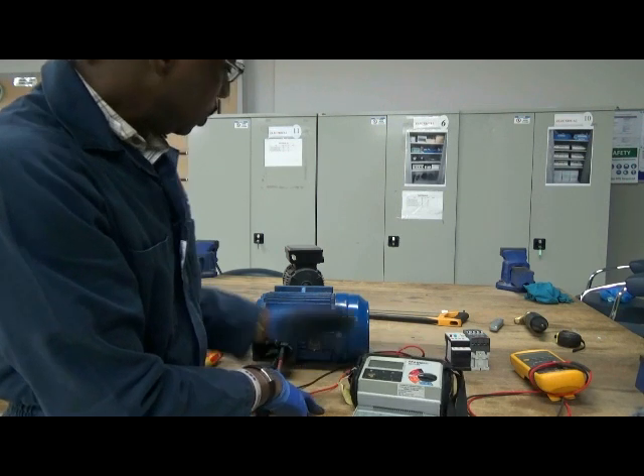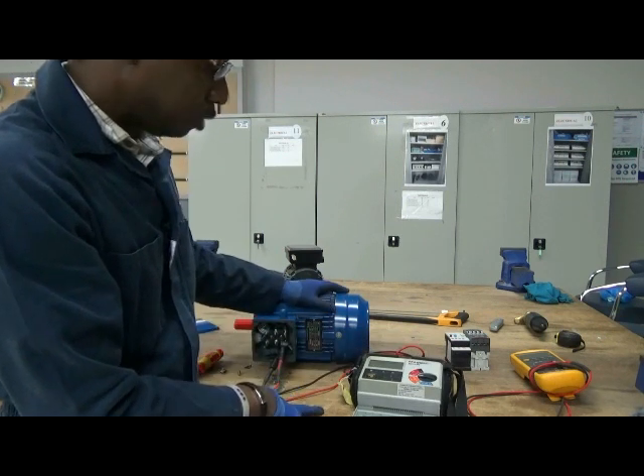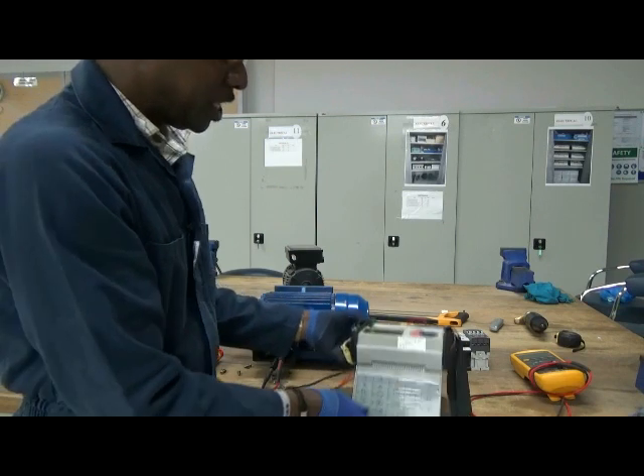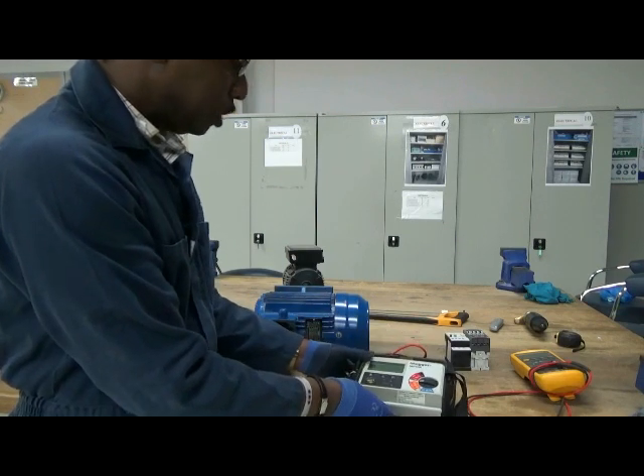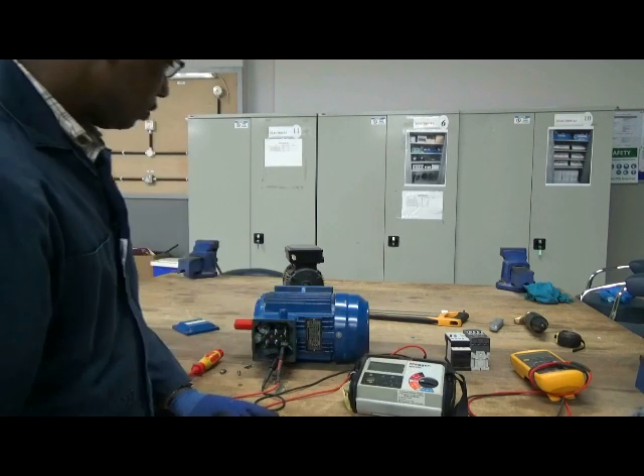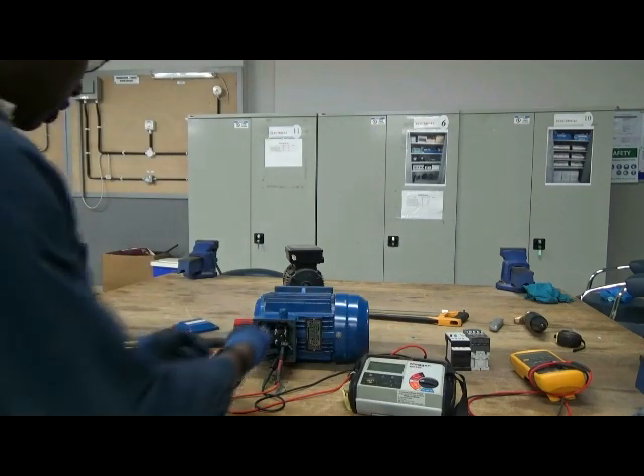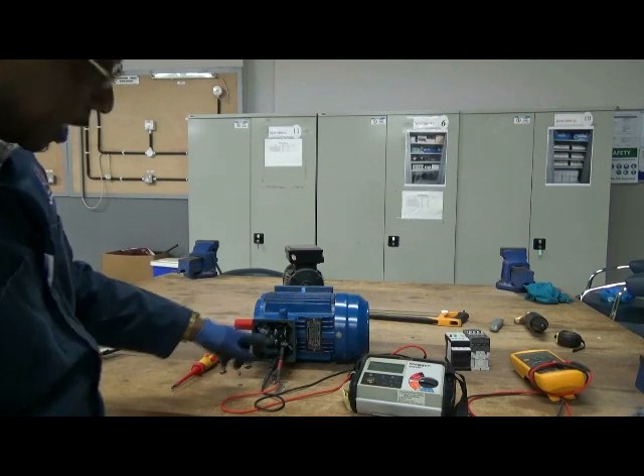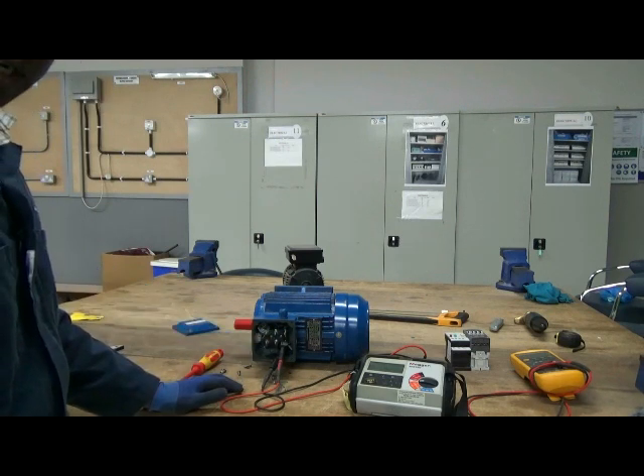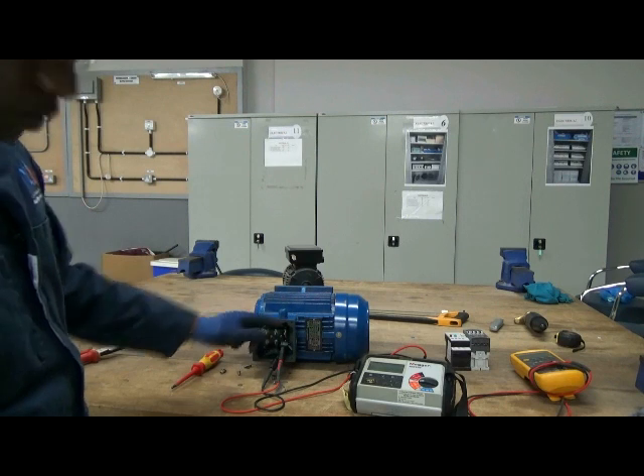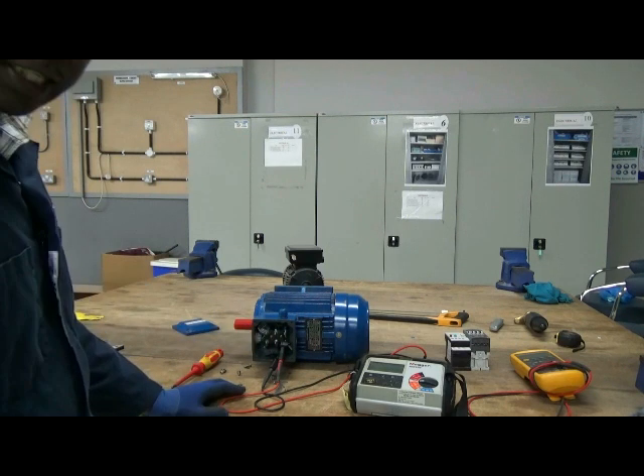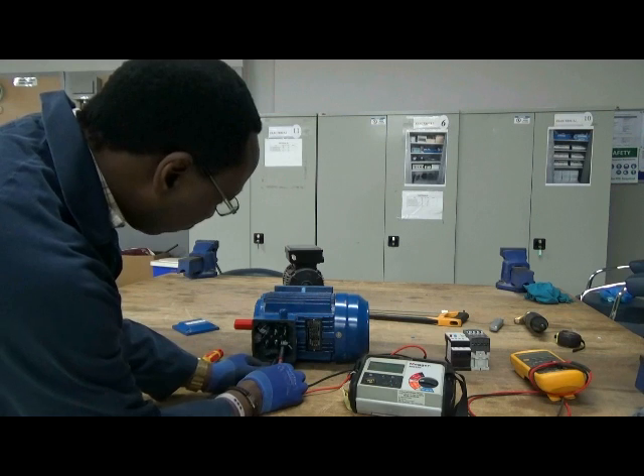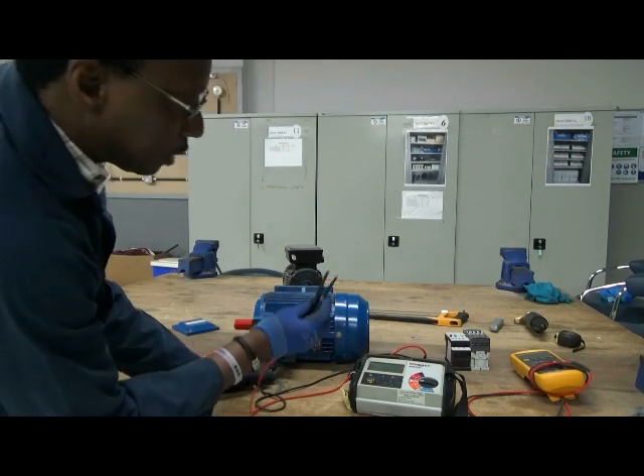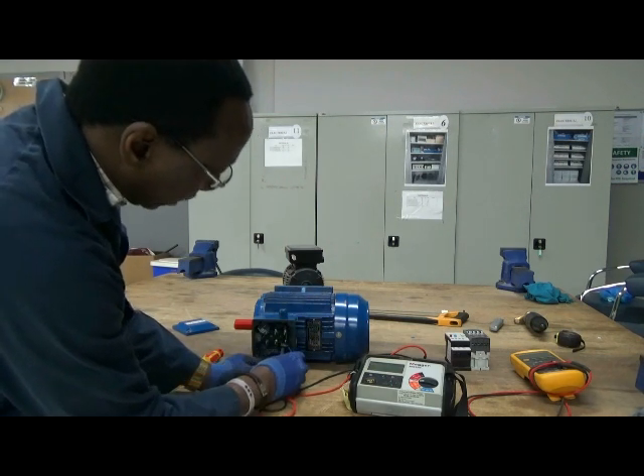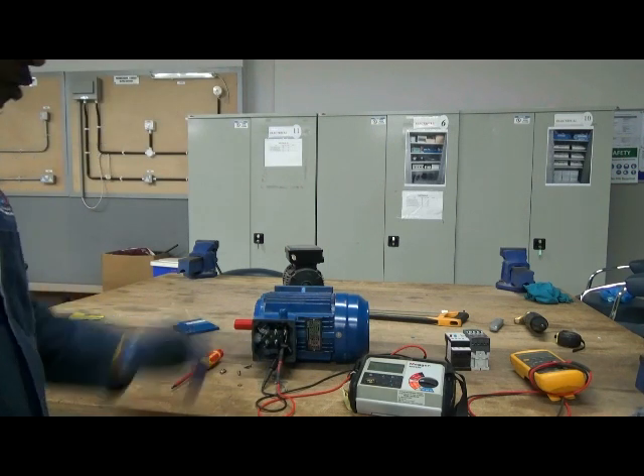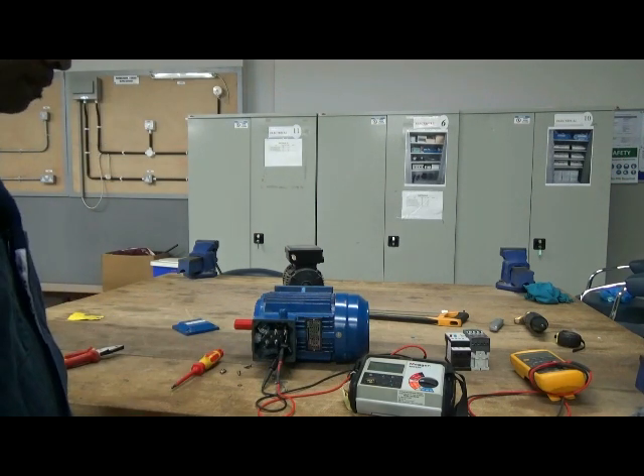I'm going to induce 1,000 volts to this machine. This is basically like a DC generator, so it can generate that voltage, 1,000 volts. So when I am testing, I have to make sure that I'm not touching the ends of the probe, because you can actually receive a shock if you touch the ends while it's testing. That's why I'm making use of these crocodile clips. I can just clip onto the winding which I want to test, leave it, and then I'll activate the instrument.